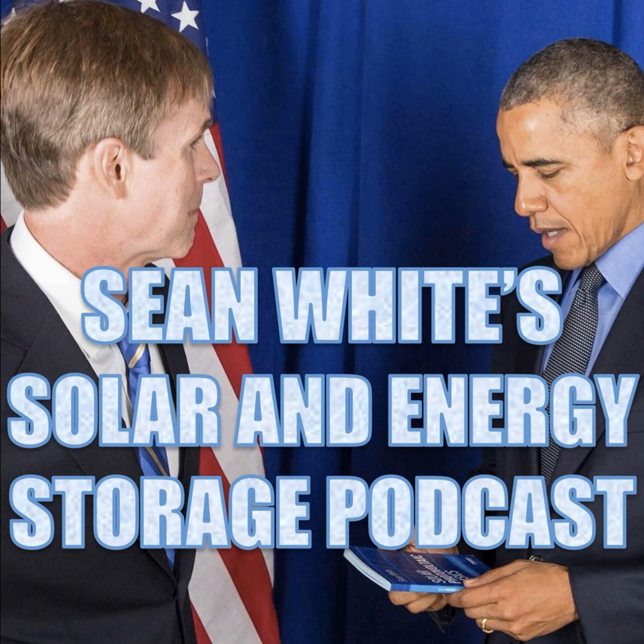And then with 311, it says medium voltage, 2,000 volts to 35,000 volts. So that is just too weird, right? So it's like if over 1,000 volts is high voltage, so 1,000 to 2,000, oh, that's high voltage. Then you get up to 2,000, oh, now we're down to medium voltage. They just contradict with each other. There's lots of different definitions. It makes things a lot more difficult when you have to apply Article 490. And so that's something that most electricians don't want to have to do.